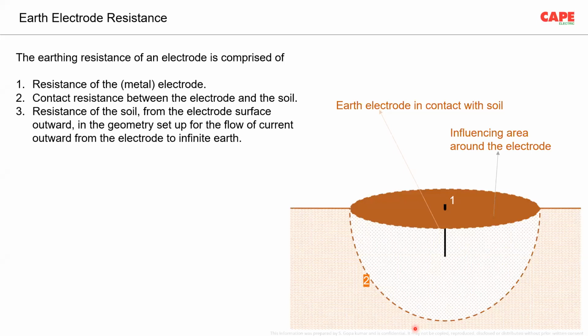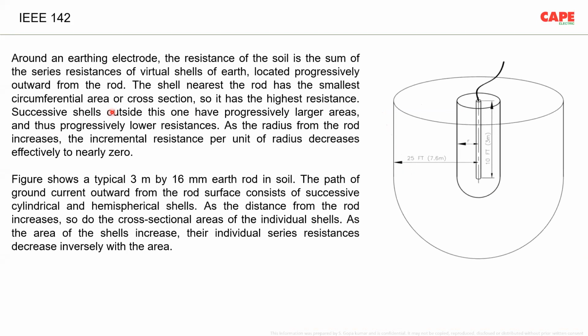Out of these 3 factors, the first one, resistance of the metal electrode, is actually immaterial because it is negligible. The second, the contact resistance between earth electrode and soil, even though we generally say that the first 2 are immaterial, sometimes the contact resistance also matters. How does it matter? For example, if you have earth electrodes in rocky areas, you dig a hole and fill the hole again with some stones. Under that condition, the earth electrode is not in good contact with the soil, and the contact resistance is high. Under that condition, number 2 is also a significant value, but generally the first 2 are neglected. The most important value influencing the final result is the soil resistivity around that particular area, which is called the sphere of influence.